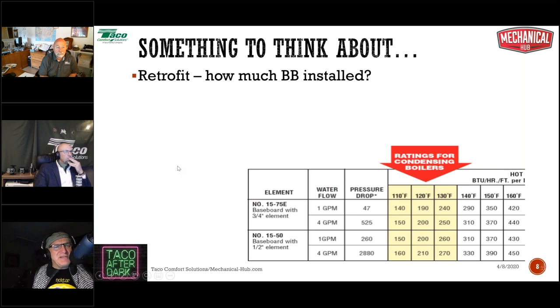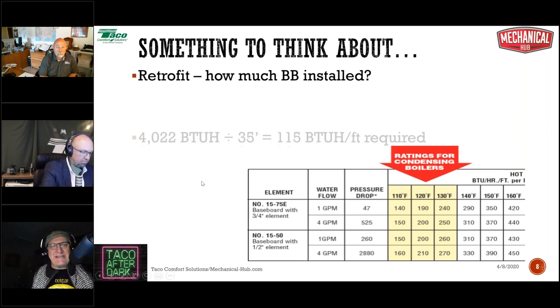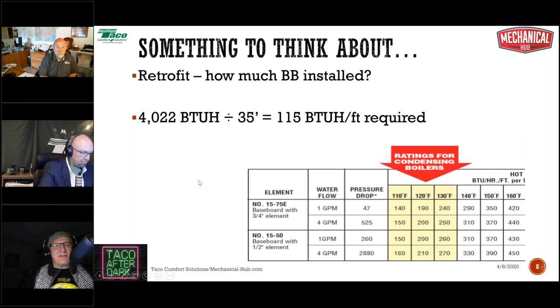So if there is, let's say, 35 feet of baseboard installed, the math here now becomes very easy. Now we just have to figure out, well, I know the heat load, 4,022. I know how many feet of baseboard is installed, 35. How do I figure out how many BTUs per foot I need? I simply divide the load by the amount of radiator installed, and I should come up with my BTU per foot requirement, all right? So if I divide the heat load, 4,022 BTUs, by the amount of baseboard installed, 35 feet, I'm down to about 115 BTUs per foot required.